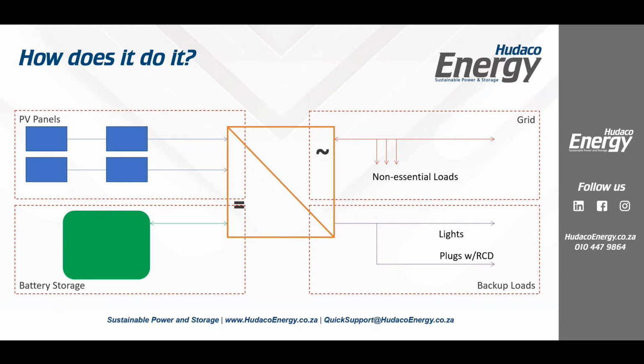Now, how do we do that without exporting to grid? Well, in your box, there's a meter supplied, and that meter gets installed here. That meter measures 2 different points. It measures voltage and it measures current. It uses the voltage to determine if and when I've got a grid failure. Of course, if there's 0 volts, I say I'm now in an off-grid state, and I move the inverter from on-grid operation to off-grid operation.